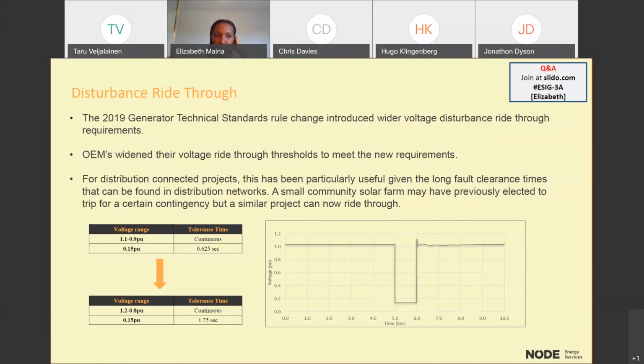So what we're seeing now, for example, on the left-hand side there, is a voltage range previously of 1.1 to 0.9, where the manufacturer would guarantee continuous uninterrupted operation for that range. With the rule change that came in in 2019, some of these manufacturers extended their voltage range, and can now operate between 1.2 and 0.8 per unit, and that's at the terminal level. The bonus for us was that even at those low voltage levels, we've gone from a 0.62 second tolerance time, and now a similar project can, for example, survive a 0.15 per unit fault for 1.7 seconds.